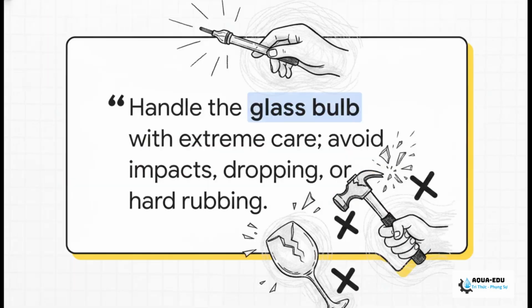Now, please slow down and be incredibly careful when you unbox the electrode. The manufacturer specifically warns us that the sensor contains a highly fragile combination glass bulb and reference junction. A single hard tap against the housing, or honestly, even just rubbing it too aggressively, will shatter that glass bulb and completely ruin the sensor before you've even started the job. Treat it like delicate crystal, brothers.